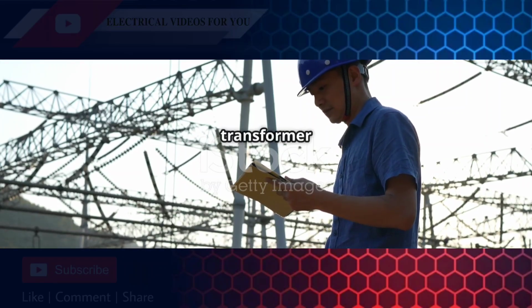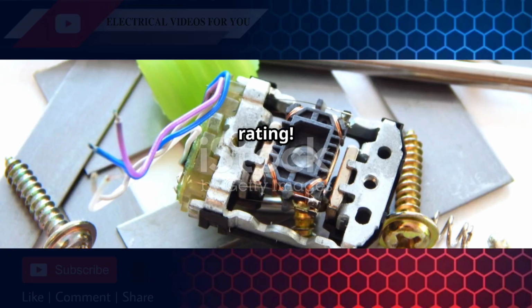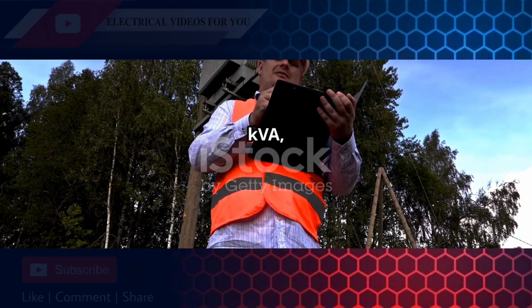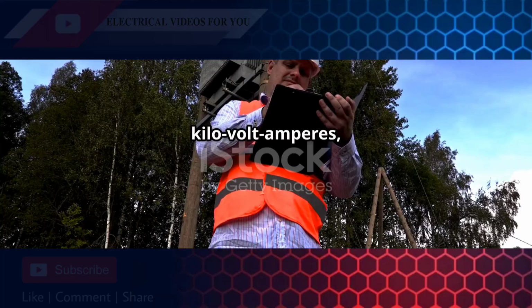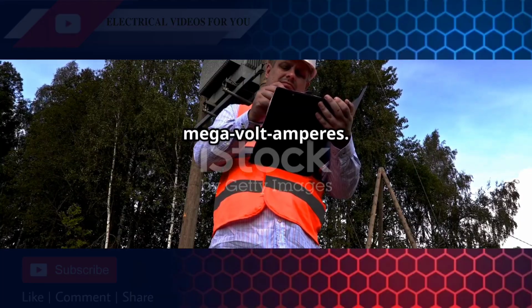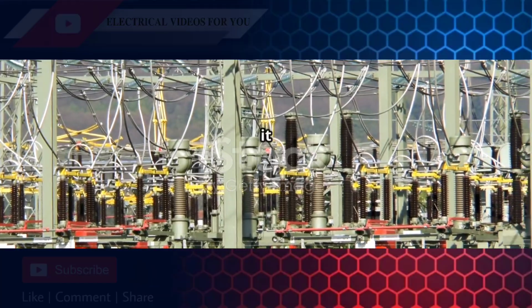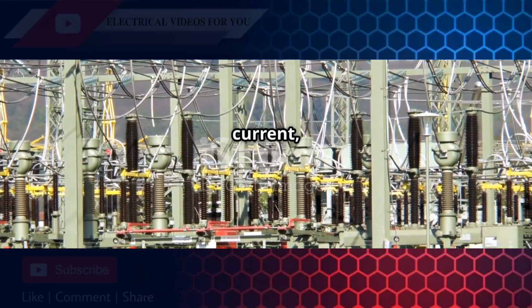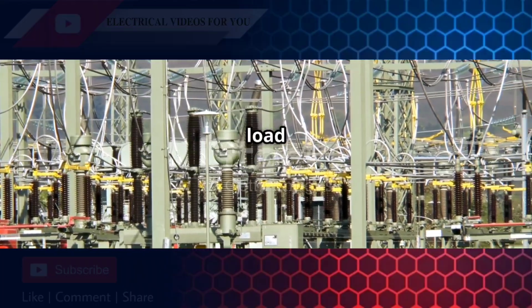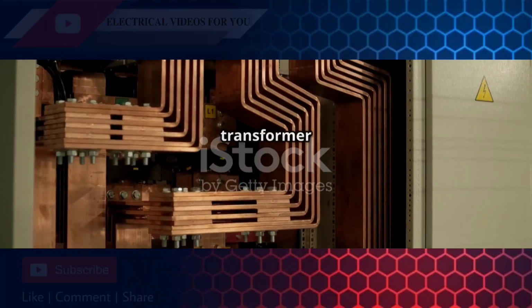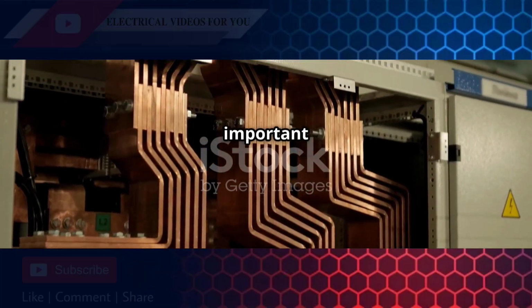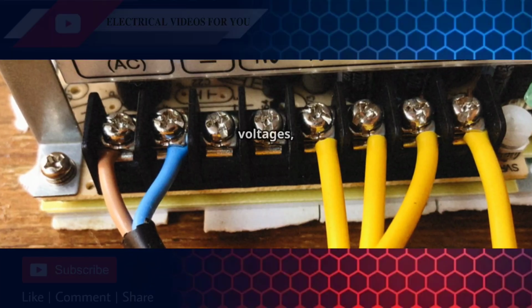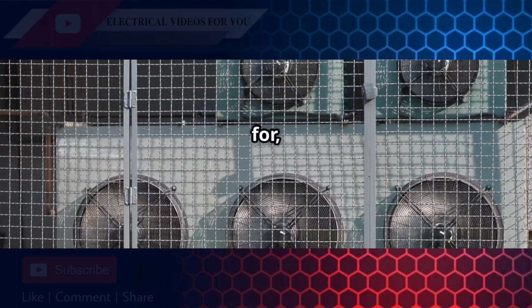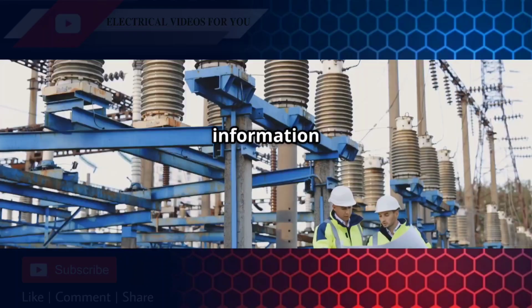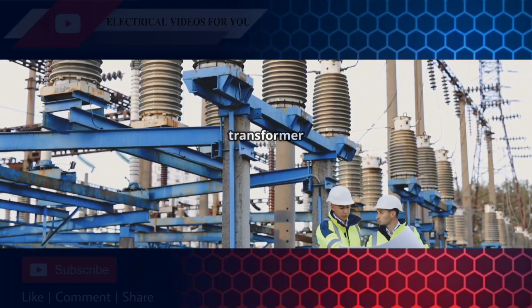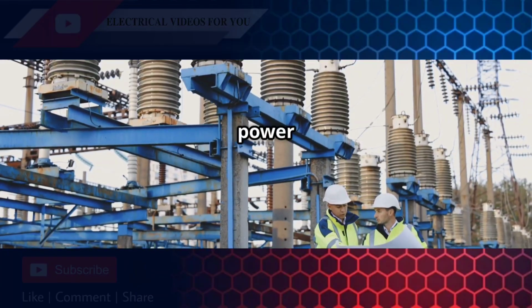How do we know how powerful a transformer is? We look at its rating. A transformer's rating is typically given in kVA, which stands for kilovolt amperes, or MVA, which means megavolt amperes. This tells you the total power it can handle, combining both voltage and current, without getting into the specifics of the load it's connected to. The rating plate on a transformer also lists other important information, like the primary and secondary voltages, the frequency it's designed for, and its cooling method. This information is crucial for engineers to use the transformer safely and correctly within the power system.